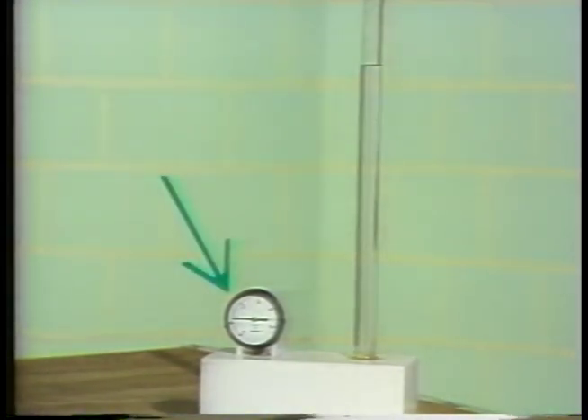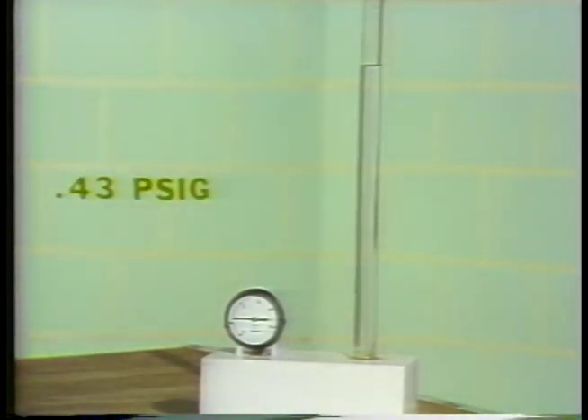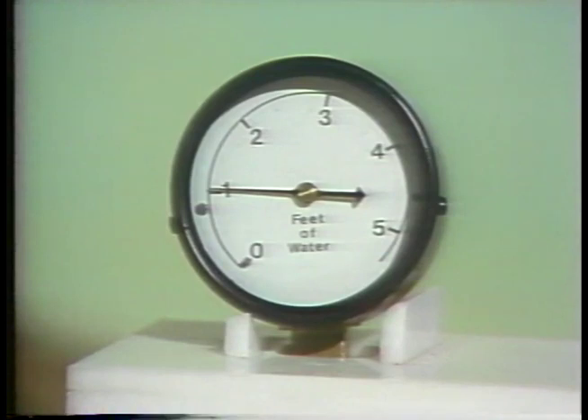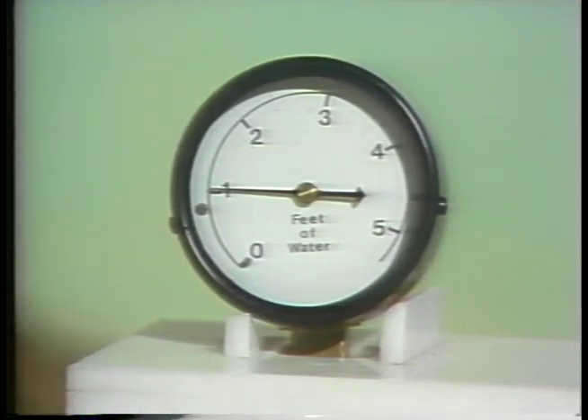Ordinarily, you might expect this gauge to indicate pressure. However, we can use the gauge to indicate level. Since 0.43 PSIG is equal to 1 foot of water, and 1 foot of water is equal to 0.43 PSIG, it is possible to use them interchangeably. What we've done is remove all of the pressure markings from this gauge and substituted markings that indicate level. Where the pressure gauge would indicate 0.43 PSIG, we've marked it as 1 foot of water. Now when water is added to the column, we can read the level directly from the gauge.